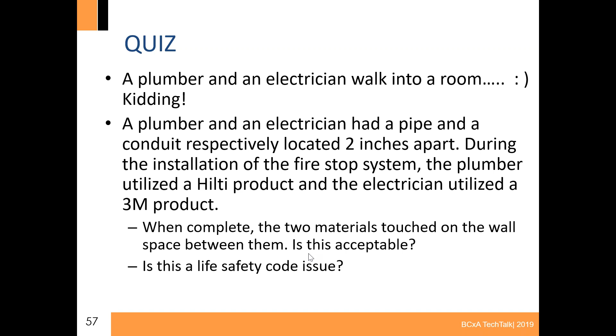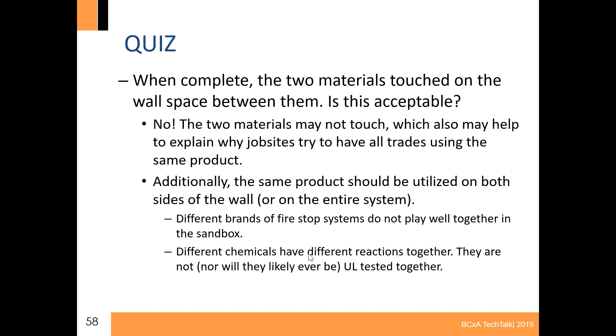It's actually a pretty simple answer, because as Rachel indicated earlier, all of these systems are tested to a UL standard to get a UL listing. None of these manufacturers are going out there saying, 'hey 3M, hey Hilti, let's test our products together to see if we have a problem.' So the simple answer is two products of two different manufacturers cannot touch each other, because there's a potential for a chemical reaction between the different chemicals in these devices that isn't the anticipated way, since it hasn't been tested.